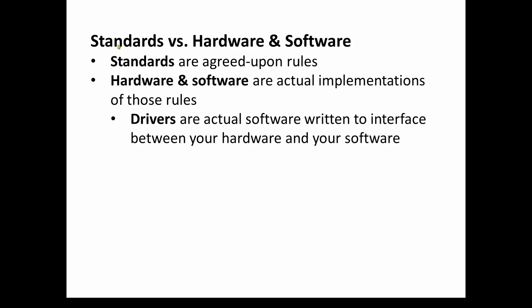Another concept that's very important is that you understand the difference between standards and hardware and software. Standards are basically written, agreed-upon rules. A group of experts gets together and decides they want something standardized with an agreed-upon set of rules to make life easier. So we know if we're going to be interconnecting our instrumentation, we all agree on how it's going to be done so we don't have 25 different variations. Standards are basically just documentation that outlines agreed-upon rules. That's different from hardware and software, which are actual implementations of those rules — if the manufacturer decides to follow them.